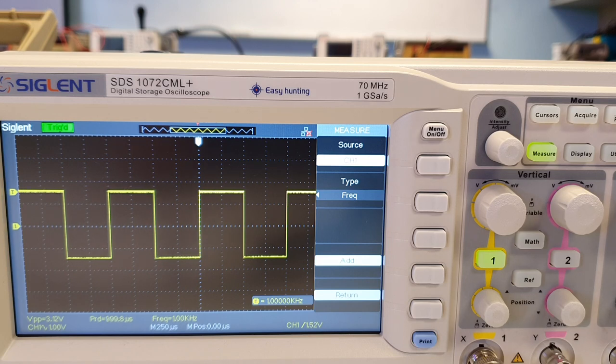The calibration is completed once you have confirmed the scope probe measurements of the pulse waveform, that is 3 volts peak-to-peak amplitude and frequency of 1 kHz.